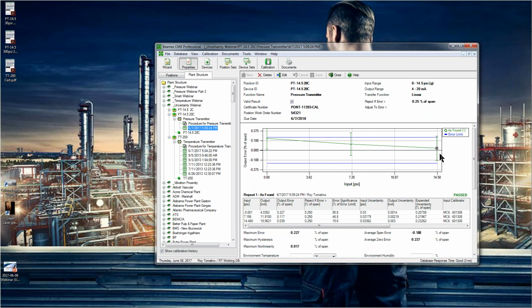And is this a good test? Is this a good recording of data? Is this a good standard to use? And the answer is no. If we look over at the first test point, the test point itself was just marginal. It just passed. But by the time we add in the uncertainty, it could be anywhere across that line. In reality, this value could be anywhere between these two dashes.